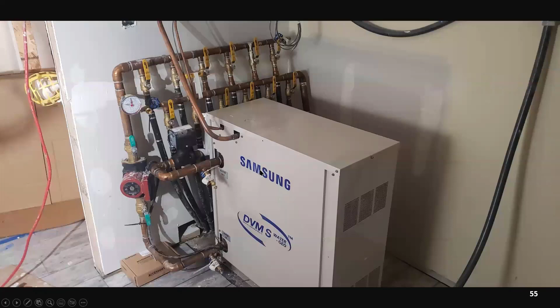These are out of order, but I'll explain why. This is an example of one of the single-phase units we installed in a residential building on the south side of Chicago. There's our loop field, a little dusty - we're not completely finished with this project in this photo. What's unique about this system, the Samsung single-phase system, is we have 8 different air handlers connected throughout this building, all cassettes in this case, in a 3-story residential building. This one unit is sending refrigerant to all 8 different air handlers.